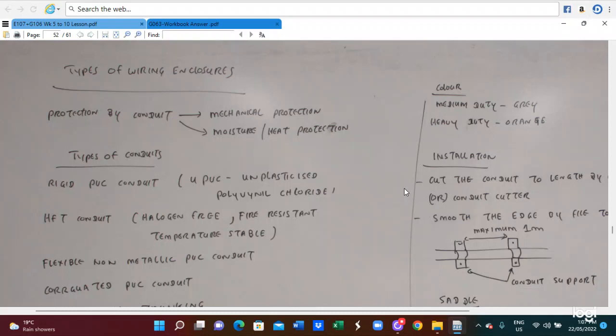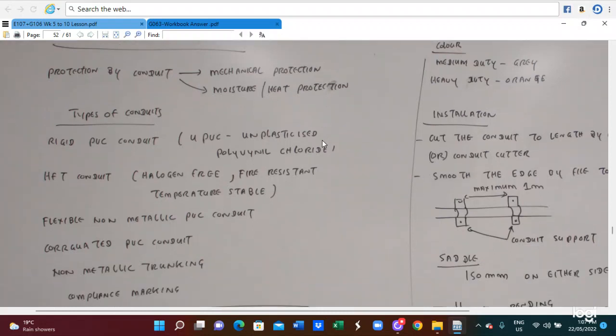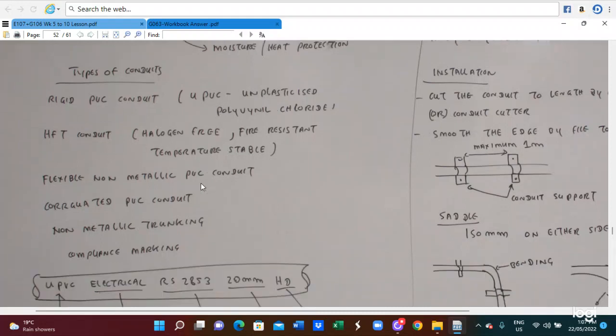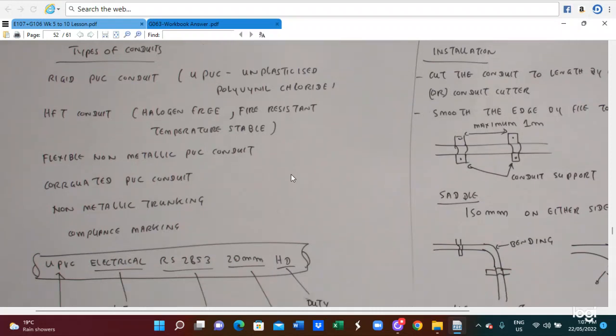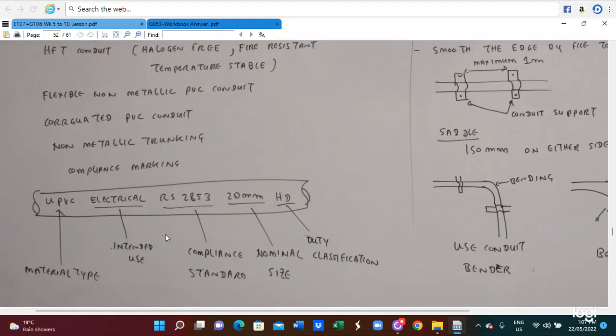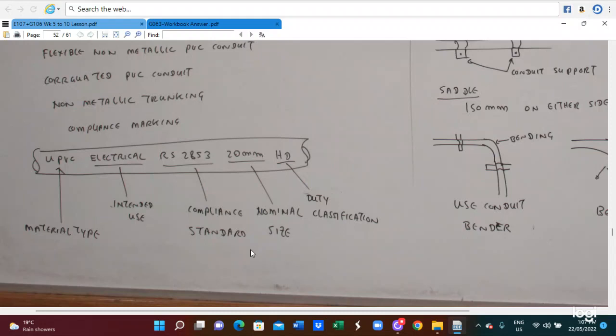The types of wiring are enclosure. Protection is provided by the conduit for mechanical protection and also moisture and heat protection. Types of conduits are the rigid PVC conduit, the HFT conduit, or the flexible non-metallic PVC conduit, corrugated PVC conduit, non-metallic trunking, and also compliance marking. So here is the specification. The first one is the UPVC. This is the material type.